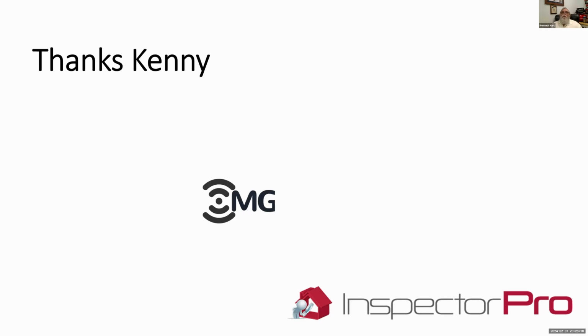In Virginia, we're required to put a statement in our reports to tell people what the concern is with the CSST that was put in a long time ago, before the code actually addressed it, and the code guys actually looked at it. For many years it was going in. Code guys weren't looking at it. The HVAC guys maybe put it in. Maybe a plumber would put it in. The electrician said, I'm not messing with it, so they wouldn't bond it or anything.